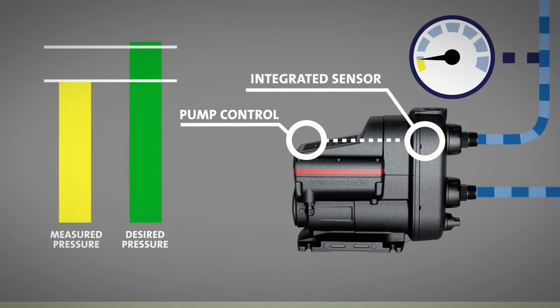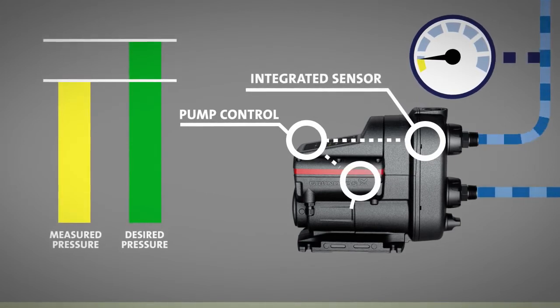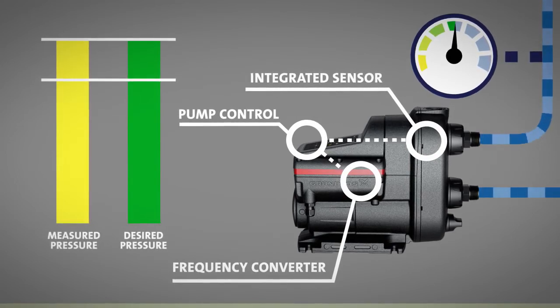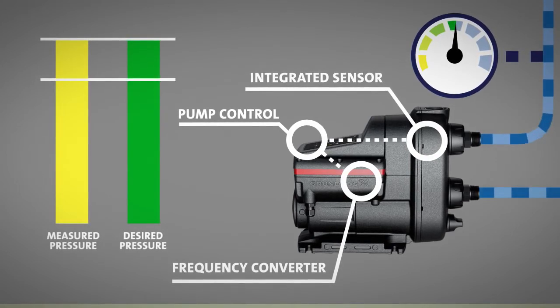If there is a difference between these two measurements, the pump control signals the frequency converter to increase or decrease pump speed and thus the water pressure in the system.